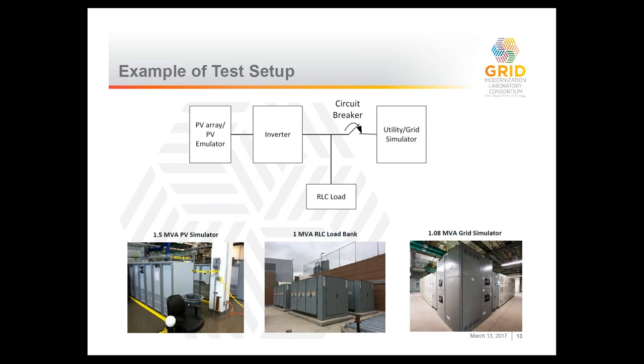This is showing an example test setup. So basically, we'll have a PV simulator or an actual PV array connected to an inverter, connected to a utility grid simulator, which can create any voltage and frequency waveform. Sometimes it may have a load connected in parallel. Obviously, it is not showing the communication here, but there will be communication talking to those inverters to change those set points and things like that.